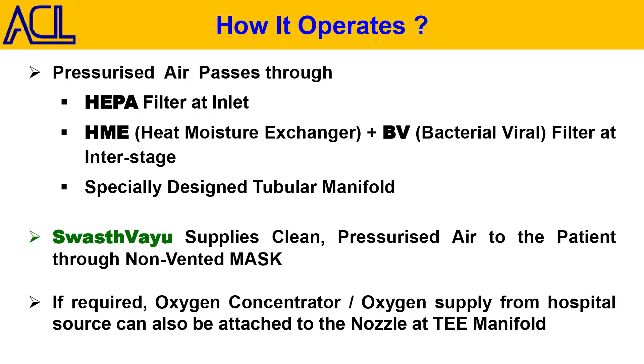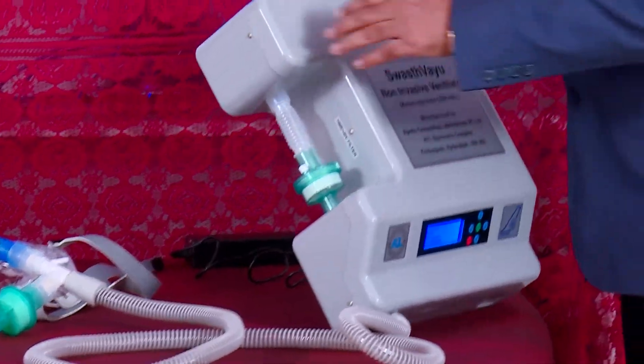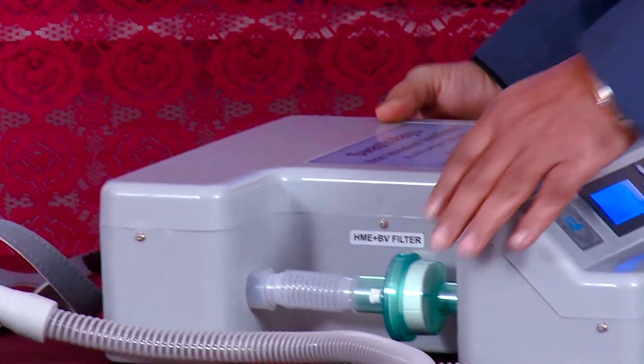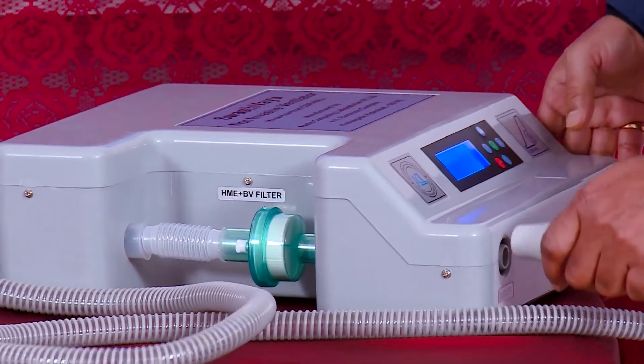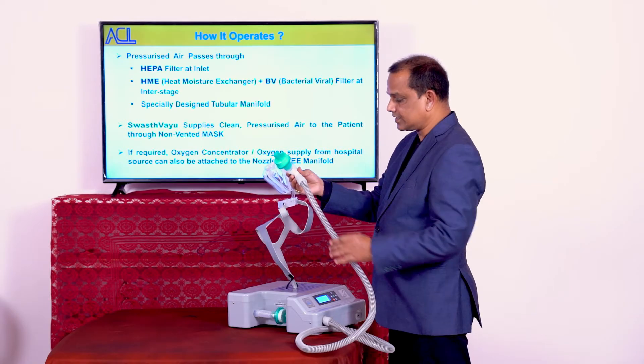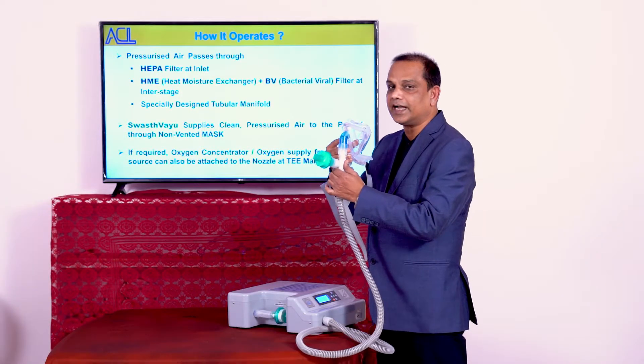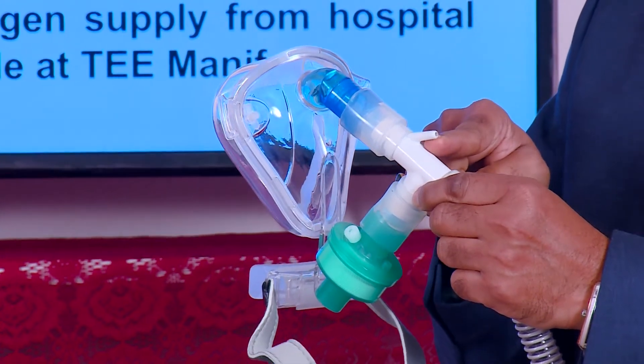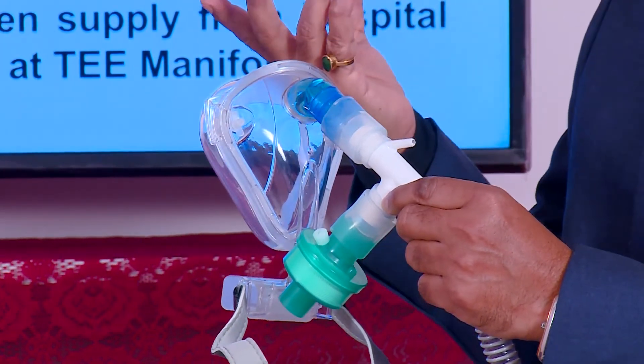The SwasthVayu ventilator operates as follows: air enters from the inlet port, passes through the HEPA filter, then through the HME plus BV filter at the interstage. The air then goes to the T-manifold and through the non-vented mask to the patient, who wears it tightly. If the patient condition warrants, there is a nozzle on the T-manifold to which an oxygen concentrator can be connected as optional equipment.